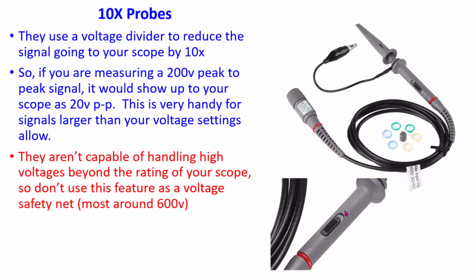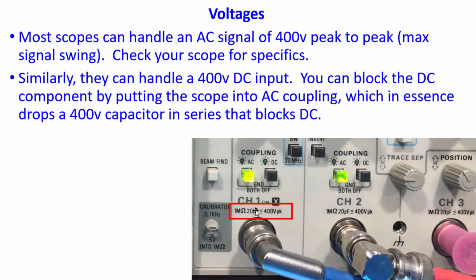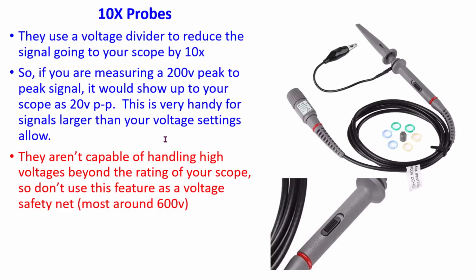So you may think to yourself, well, heck, if my oscilloscope says 400 volts peak, and I just put a 10x probe into it, well, that's easy. Now I can measure 4,000 volts. Unfortunately, it doesn't work like that, okay? These probes are not capable of handling that type of voltage. The voltage divider inside of this has components that can't handle those kind of voltages. So in most cases, you're limited somewhere around the voltage going into your scope. I actually looked this one up on Amazon, and it says it can handle about 600 volts. So you might get by with a little bit more by using your 10x probe. You're not going to get 4,000 volts feeding into your probe, into your scope, and measuring it. You will fry some things along the way.